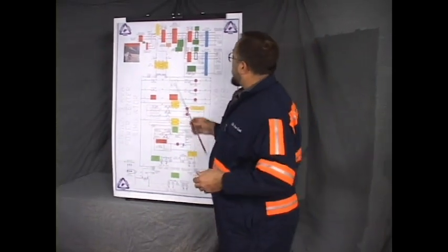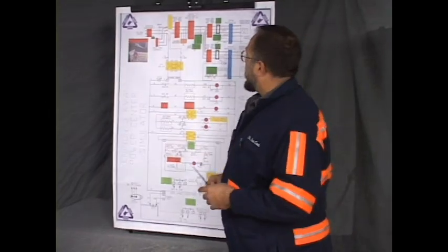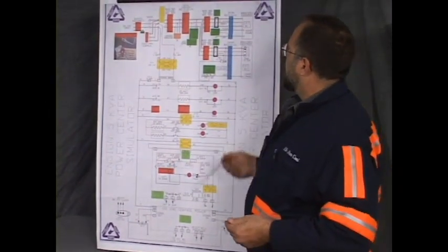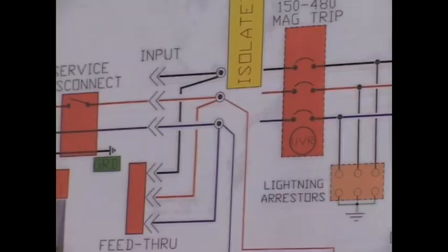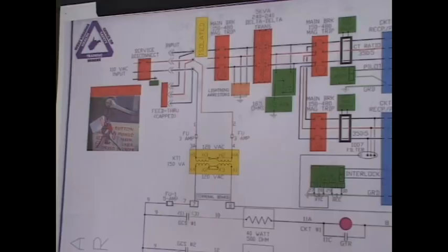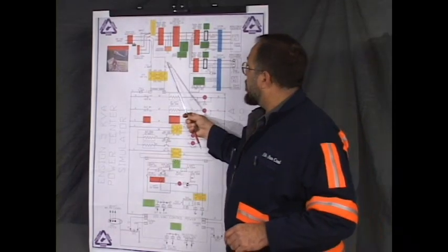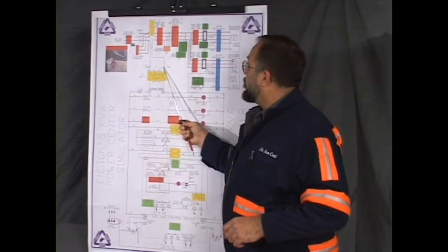Now, by the primary not being energized, that would lead you to believe that somewhere between where the primary circuit originates at the input and the primary of the transformer, we have a cable fault or a problem in either a wire or a fuse.